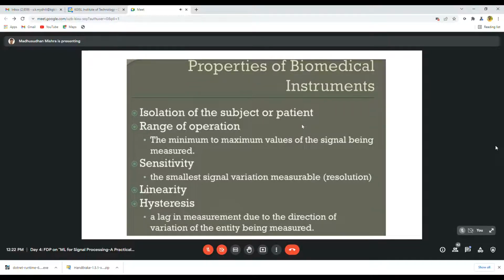We have to keep many points in mind. One is isolation of the subject or patient - the instrument should completely isolate so the person is safe and comfortable. Then range of operation, which refers to the minimum to maximum values of the signal being measured - this range should be suitable. Then sensitivity, which refers to the smallest signal variation that can be measured or detected by the instrument. Also linearity, and hysteresis - a lag in measurement due to the direction of variation of the entity being measured.